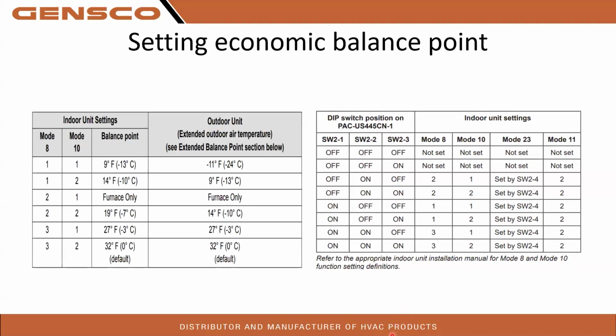One of those dip switch and function settings you guys are going to need to do is setting the economic balance point. The economic balance point is the outdoor ambient temperature at which the system switches over from heat pump to gas furnace automatically. So that is adjustable. Economic balance point can be set through your MHK2 using modes 8 and 10, which is normally for static pressure settings, but because we don't have control of the fan static, those settings have been repurposed for the economic balance point. So you'll find this chart right here in your PAA Coil Installation Manual. Look under the economic balance point section.